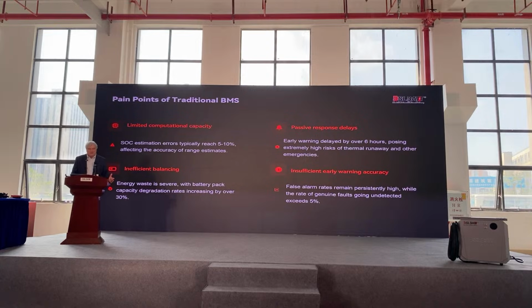With this new setup and this new parallel, how we put this unit together, we've now got an SOC. Estimated errors typically are 5 to 10%, affecting the accuracy of the range and the limits. Inefficient balancing, energy waste is severe, with the battery pack capacity degrading rate increasing by over 30%.